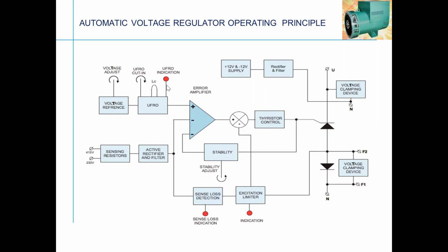So this under frequency roll off has been set in the AVR, where AVR knows what time I have to feed the excitation, or what time I should increase or decrease the excitation based on that, or whether the RPM or the load. So this fellow plays an important role to match the voltage, so UFRO, and that is part of that system. So it gives a command.